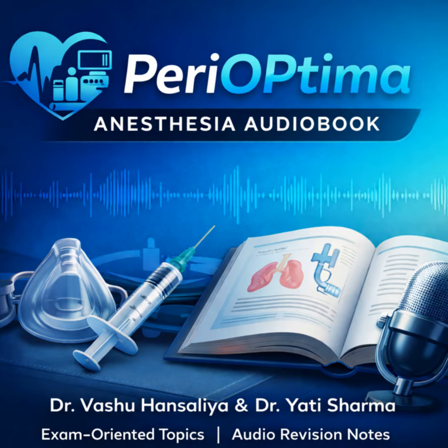Right. So open systems are pretty much historical, like simple insufflation. No bag, no rebreathing, very little containment. Semi-open systems have minimal or no rebreathing, and some ambient air might even be drawn in. Think Mapleson E, or Mapleson A or D when your flow is extremely high. And semi-closed, that's where most modern practice sits, isn't it? It is. Semi-closed means partial rebreathing happens, and the excess gas is vented out to the atmosphere or a scavenger through a valve. This is the definition of a standard modern circle system at typical flows, say 1 to 2 liters per minute. It's also how the Mapleson systems operate when the flow isn't quite high enough to prevent all rebreathing. Which leaves closed systems.